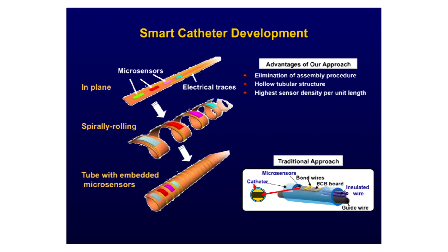So, as I mentioned, you take a strip and then you implant a bunch of sensors into the strip, then you spirally roll them, and as I mentioned, you can have these sensors both on the outside as well as on the inside of the strip. This is in contradistinction to the traditional approach where if you had a sensor on a catheter, you'd have to have a bunch of wires coming from that sensor and going to the monitor outside. And those wires, of course, traditionally are somewhat bulky, and so the lumen of the catheter tends to get smaller, and it makes the device bigger and bigger, and you don't want that device to be too big because remember you're sticking it through the brain into the ventricle. So not necessarily smaller the better, but to a certain extent smaller the better.